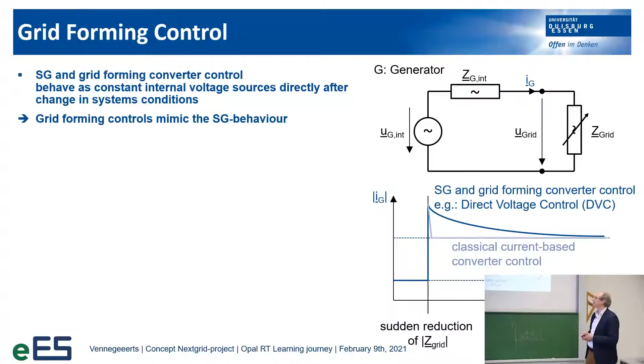Nevertheless, it's not just mimicking synchronous generator behavior. For a synchronous generator, the main parameters, for example the mechanical inertia, are given just by the design of the synchronous generator. Now we are dealing with control, so we can almost program every kind of behavior and control and its parameterization. Therefore, there's ongoing research all over the world, and also at my institute, on desired grid forming behavior in the long run when we have 100% renewables. But this behavior must also cope with the transition period when we still have classical equipment and new equipment. There might be new stability issues and limits possible, because we have a next generation grid with next generation behavior, and we have to investigate this.